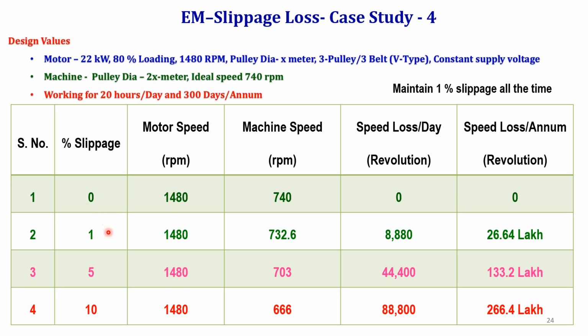Suppose the 1% slippage persists in the system, then the motor speed will not change because I'm applying a constant voltage here. That's why I mentioned it. But the machine speed will drop by 1%. So 1% is 7.4 RPM. Therefore, the new RPM for the machine is 732.6.